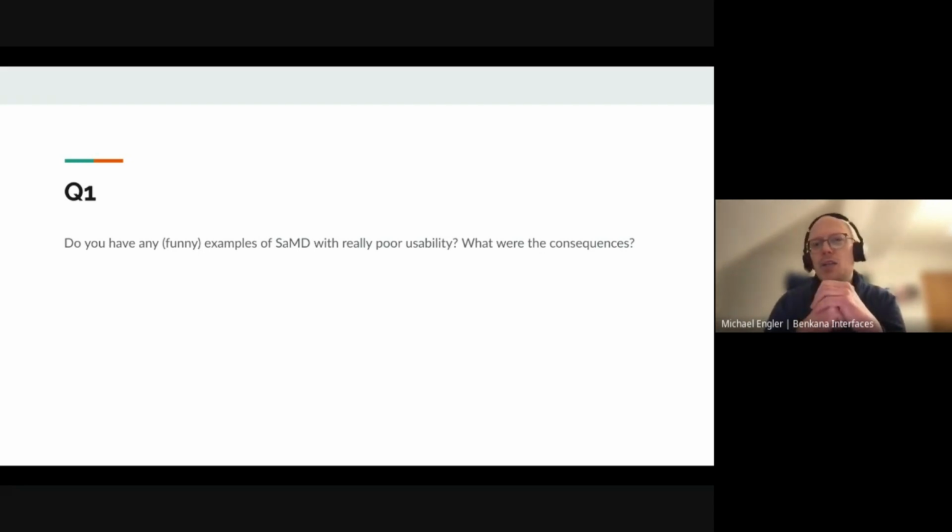That button switches the ventilator on and off. And what happened was that someone pushed the button to start the ventilation again, but instead of starting it, switched it off completely, and the patient died.